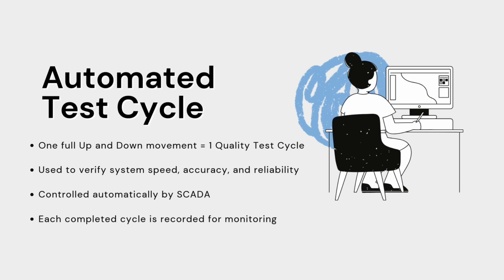So I'll continue with the process of the controller, which is the sequence. For the first part, the automated test cycle. In the system, one complete extension and retraction of the cylinder is considered one test cycle. The goal is to ensure the system operates smoothly, consistently, and within the required time limits. SCADA controls the entire sequence and records each cycle for performance monitoring.